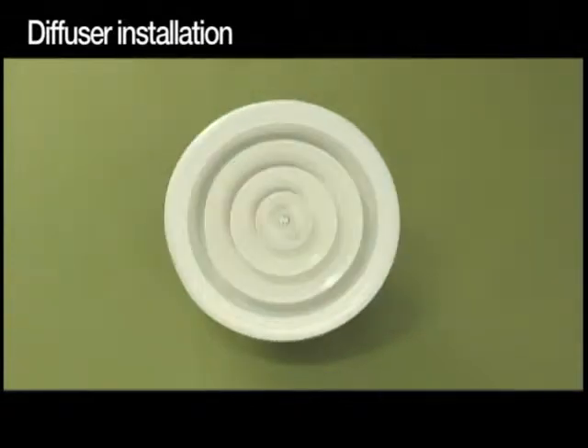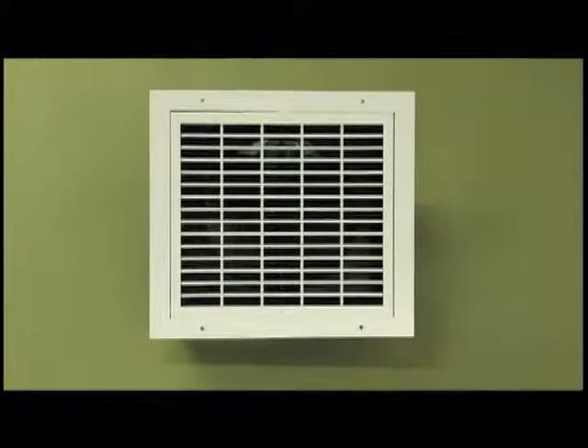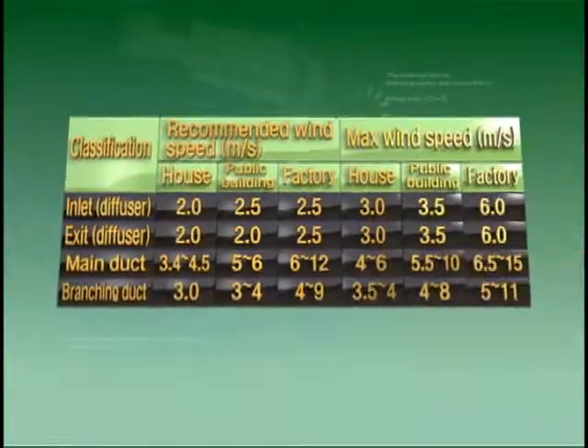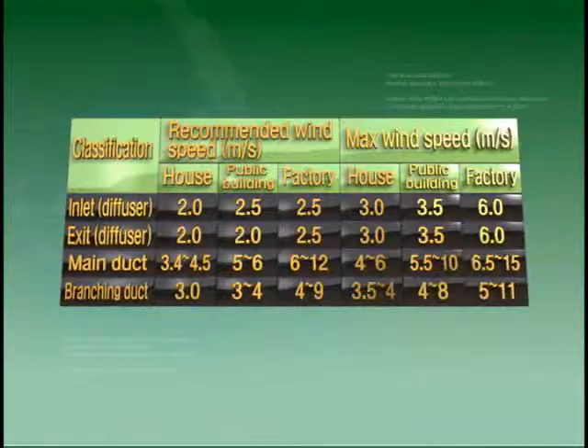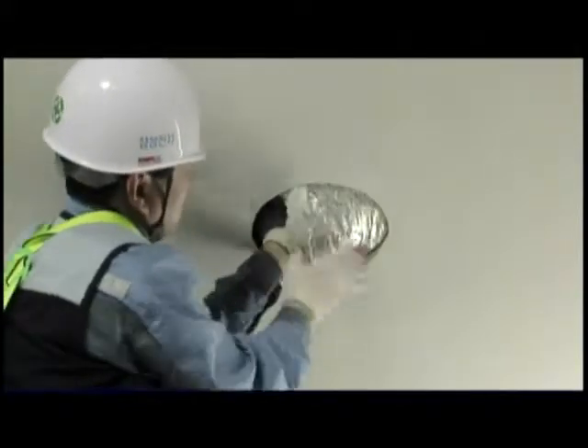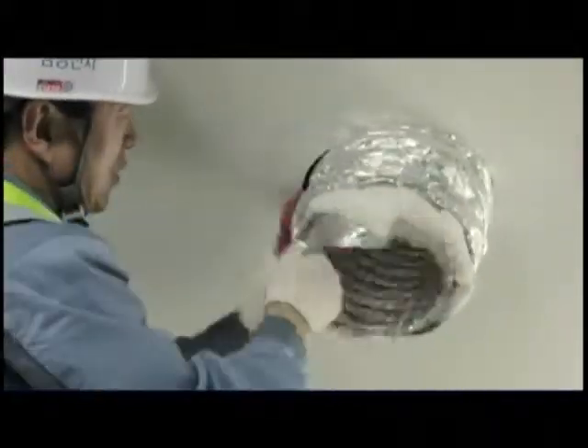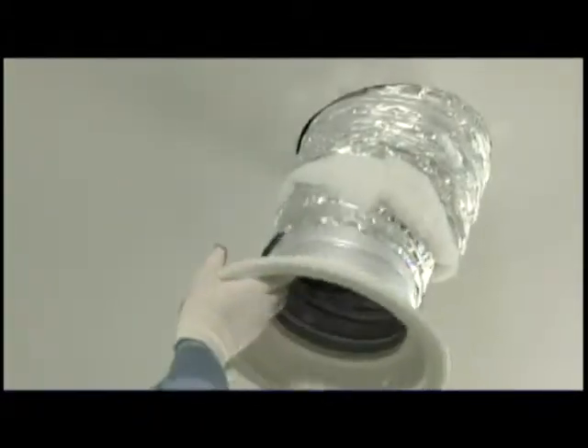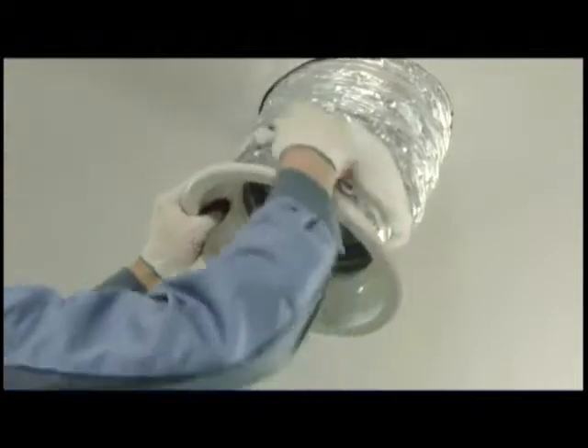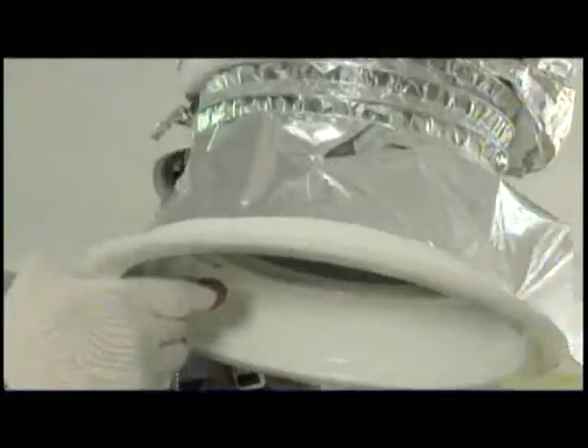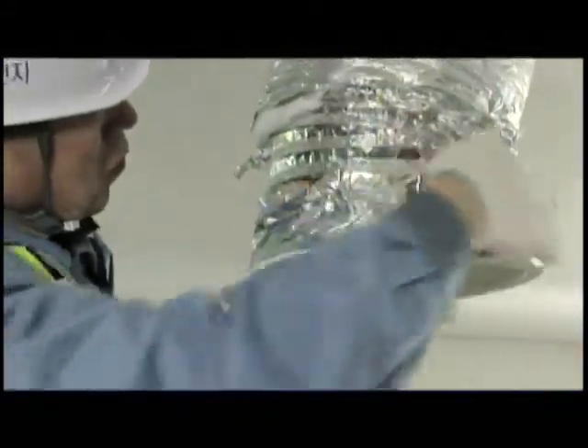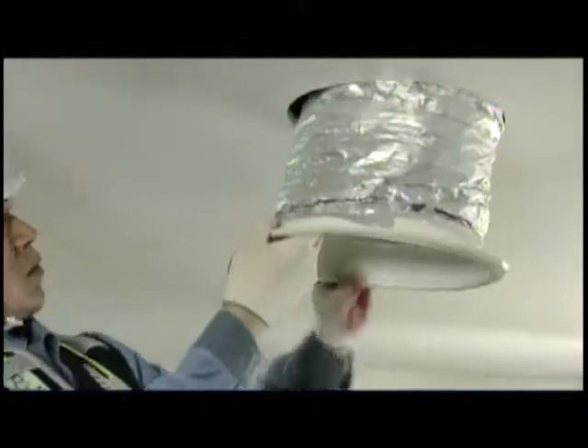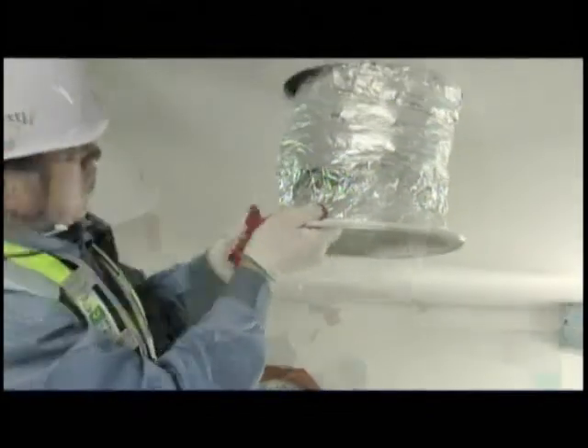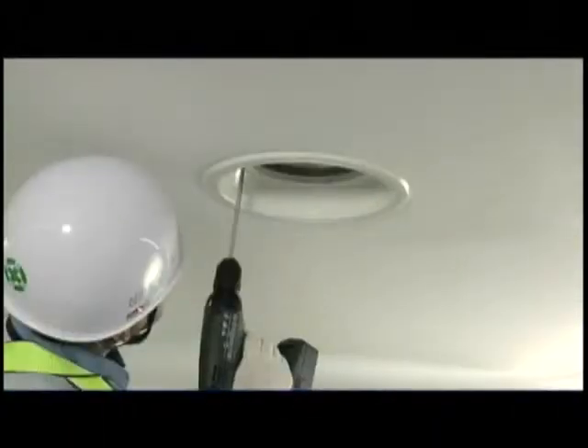A diffuser of an adequate size should be selected to prevent noise and cold drafts. Punch a hole suitable for the size of your diffuser in the mounting location for your diffuser. Fix the diffuser and the flexible duct with a clamp and use aluminum tape to finish the joint areas so that you can prevent air leakages. Then fix the diffuser on the ceiling.